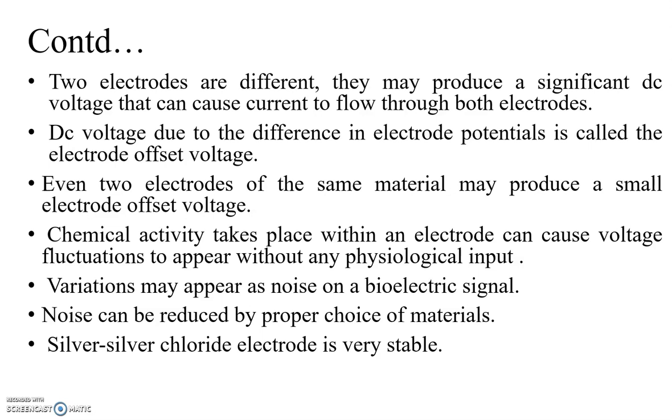The chemical activity that takes place within an electrode can cause voltage fluctuations to appear without any physiological input. This variation may appear as noise on the bioelectric signal. The noise can be reduced by proper choice of material. Silver chloride is a very stable one.